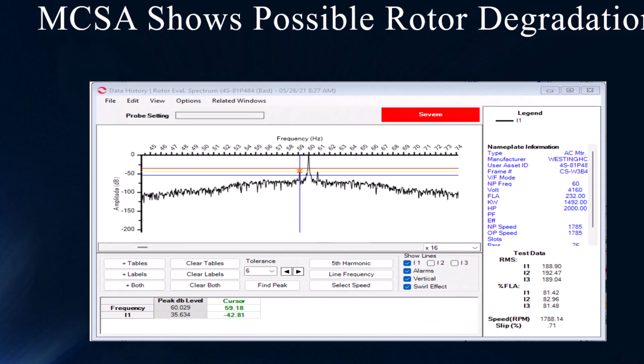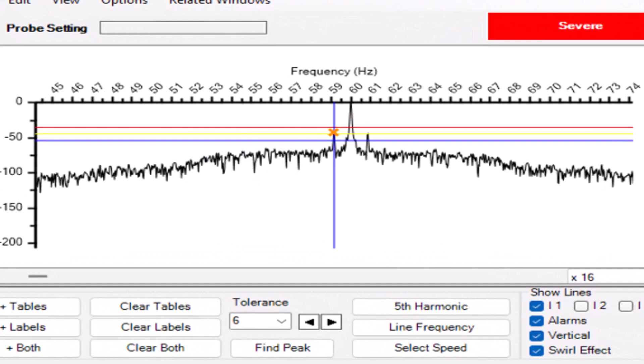So this was the test that shows the possible rotor degradation, and we've gone through a tremendous number of rotor bar anomalies. We always tell you a couple things: minimize starts and stops. Why? Because that's the most stressful time for that asset, going through 7 times the running current of a motor. But there's also other things.